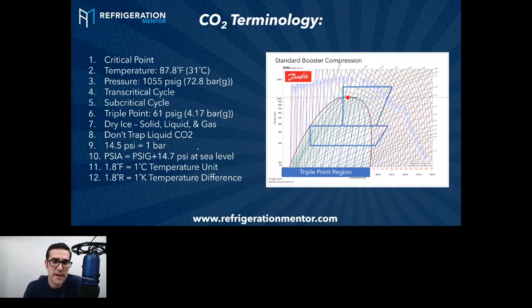There are also a few terms you'll hear over and over with CO2 as a refrigerant, even in a heat pump—something called the critical point. This is a key difference between CO2, or R744, and refrigerants you may work on today like 410A, R22, or newer A2Ls like R32 or 454B. Every refrigerant has a critical point, but CO2 has a very low critical point.